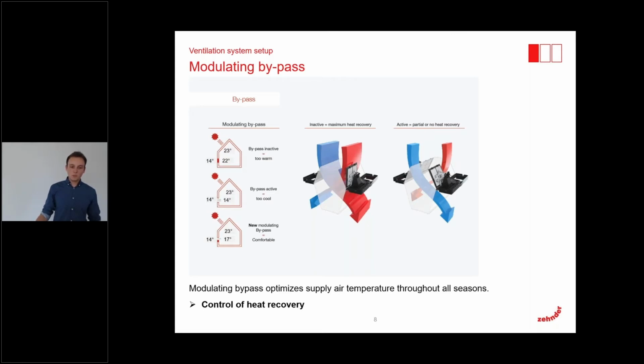Now we developed the modulating bypass, which regulates the amount of heat recovery and the bypass. So we can mix these two airflows and we take in the air at a temperature of 17 degrees. So that's the optimum temperature. And this is done by two flaps that cover the heat exchanger in a way to regulate the airflow going through the exchanger. So what we have here is a control of heat recovery to get an optimized supply air temperature.